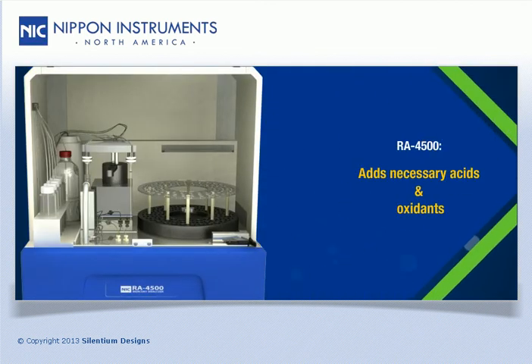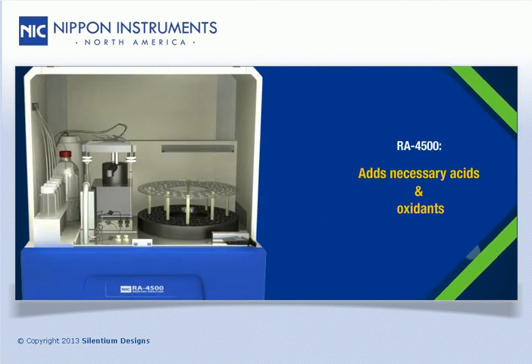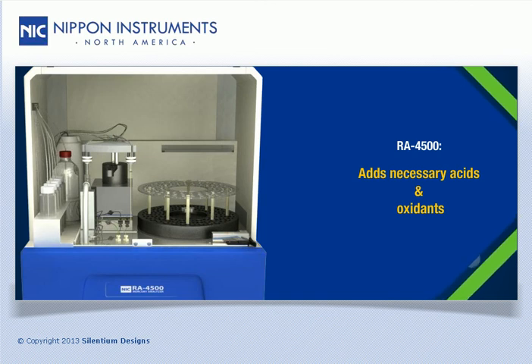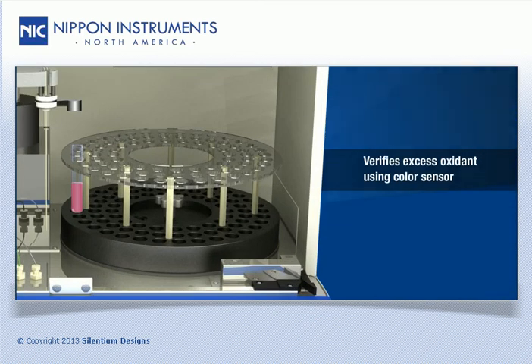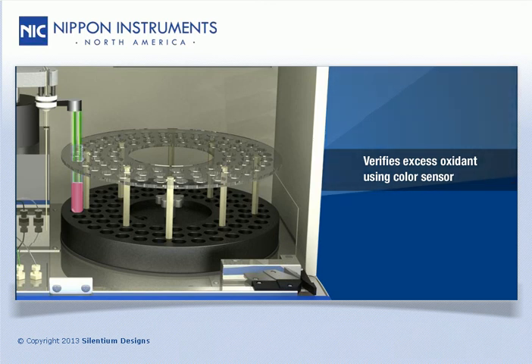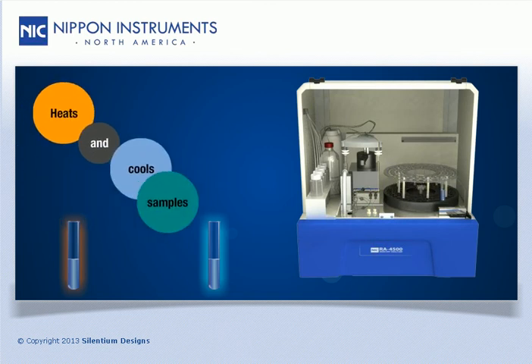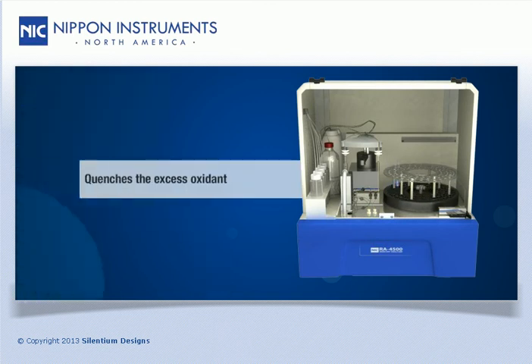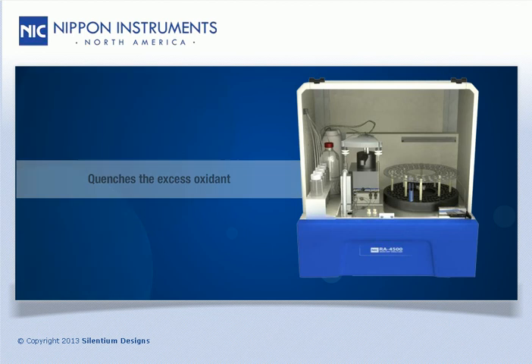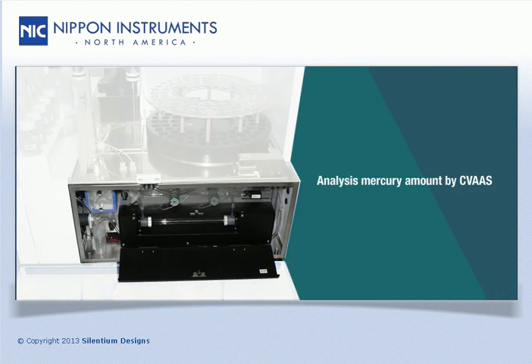The RA4500 accurately and precisely adds all necessary acids and oxidants to each sample, verifies the inclusion of excess oxidant with a built-in color sensor, heats and cools all samples, quenches the excess oxidant, and then performs mercury analysis by CVAAS in one fully automated, seamless, and unattended operation.